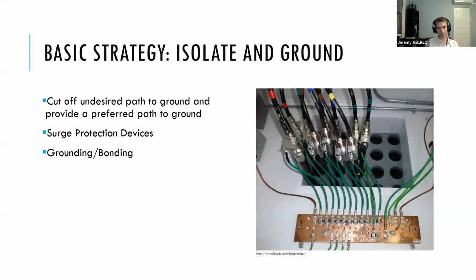The way we isolate is with a surge protection device. We're going to go through in detail some different types of SPDs, and those cut off those undesired paths. Some of those undesired paths are coaxial cable and electrical lines, things that are conductors, but in this case, we don't want them conducting. We don't want them bringing that surge towards our equipment and towards us. And then the way we give it a better, preferred, or designed path to ground is through grounding and bonding.